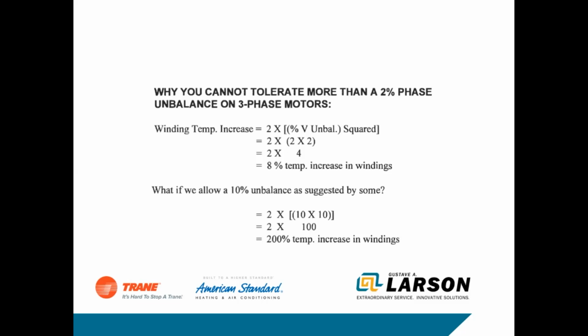So the big deal here is, as the voltage imbalance increases and the amp imbalance increases, the windings start to run hot. So that could be a big issue. And if you're talking about a 3D compressor or a 4D compressor, that's a lot of heat, and that's not a cheap compressor to replace. So again, it is a big deal. So if you're on 3-phase systems, just make sure that you take a good look at the voltage imbalance.